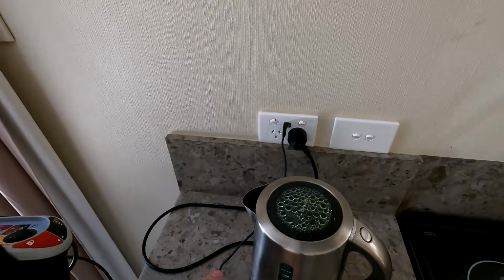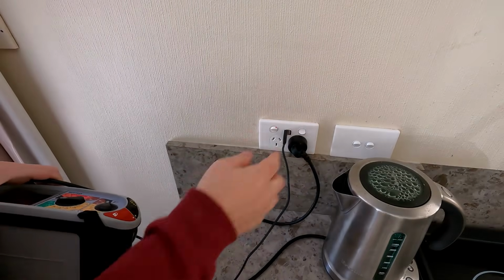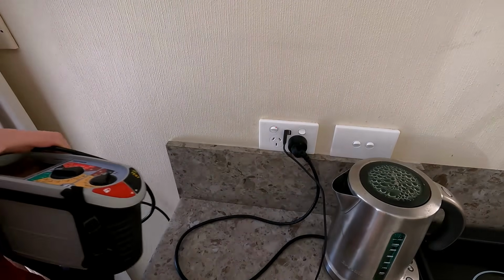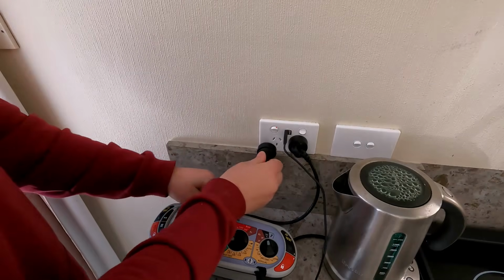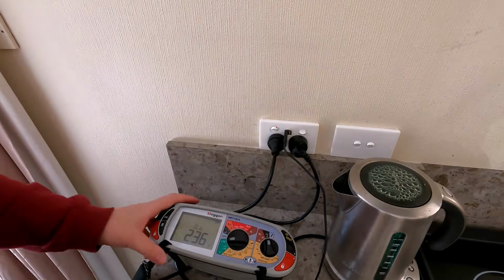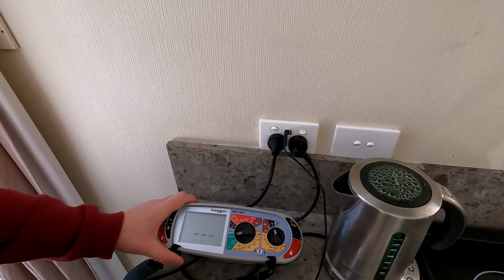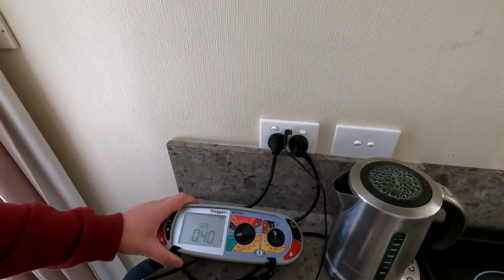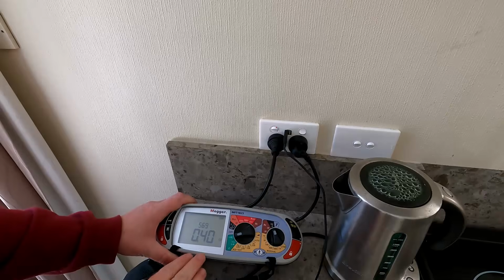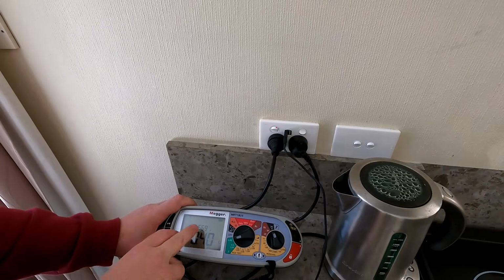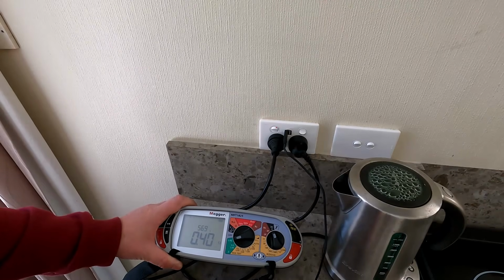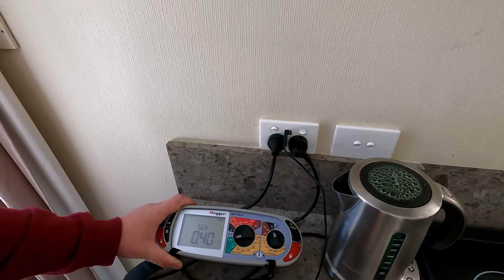1.05 ohms. So what I've got here is a socket that's much closer to the point of supply. So I'll just do one here to show you what sort of results we do expect. And there we go, that's a much lower impedance. It's much closer to the point of supply. And of course there's a higher prospective fault current that's going to be produced.